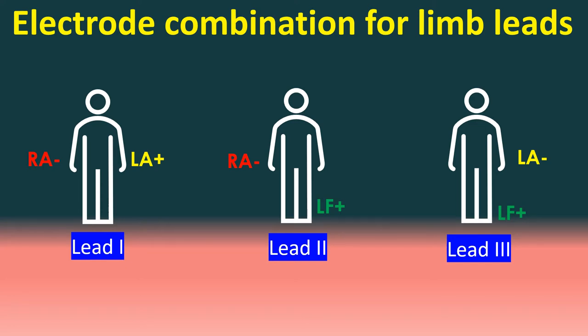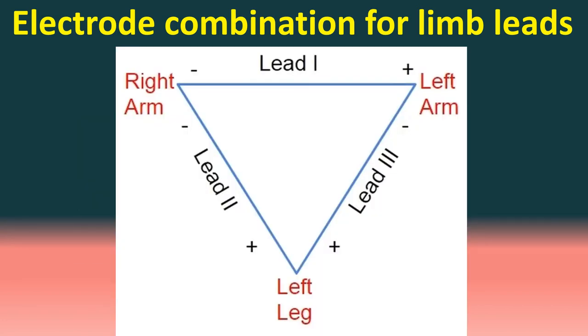Lead 1: left arm positive, right arm negative. Lead 2: right arm negative, left foot positive. Lead 3: left arm negative, left foot positive. A diagram illustrates the positive and negative poles of the three standard limb leads. Note that the right arm is negative for leads 1 and 2, and the left foot is positive for leads 2 and 3.